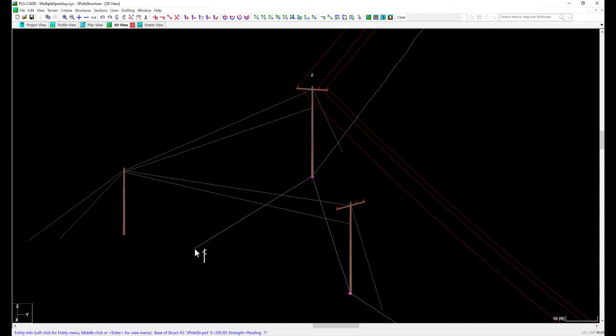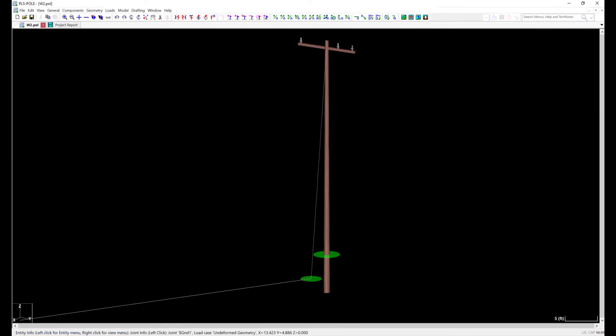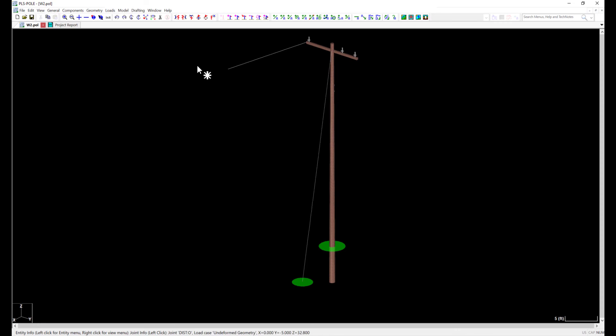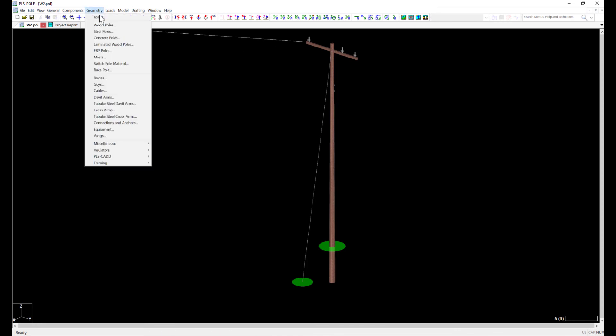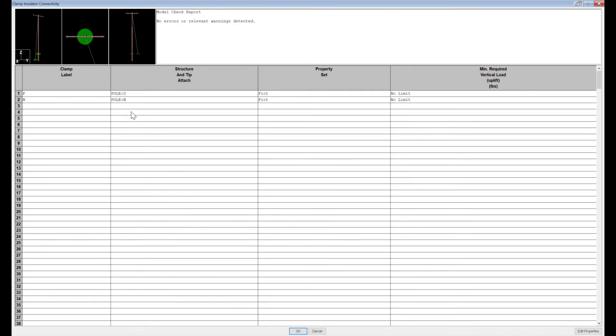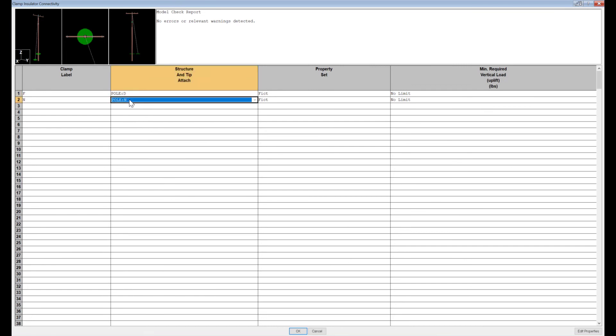I'll first go to a structure model with a conductor carrying pole. In my clamps geometry dialog found at Geometry, Insulators, Clamps, I can add clamps on this pole to attach the steel wire to. My attachment heights are the same as I was using for span guys, which I added in the wood pole geometry dialog.